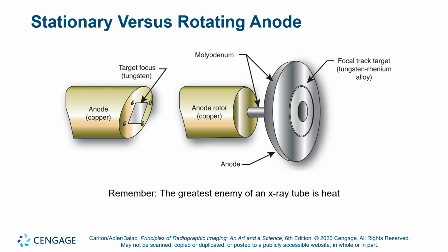So, what is the improvement in design? Why do we use rotating anodes? Because they have greater heat capacity. So the heat capacity of a rotating anode depends on the focal spot size, that is the effective bombardment zone or the actual bombardment zone, the thickness of the wheel itself, how much mass of graphite it has, and how thick the molybdenum layer is. Those determine the capacity of heat that can be absorbed instantaneously. And then the speed of rotation is also proportional to spreading out the bombardments, and so more effectively distributing the heat, so it marginally increases heat capacity of the rotating anode.